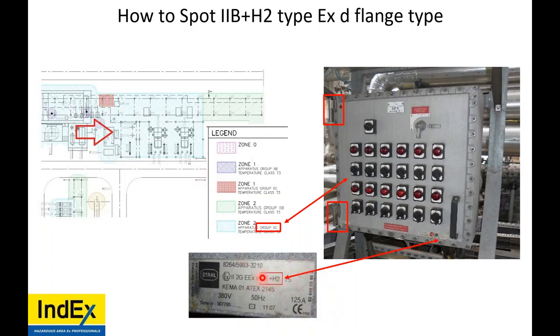Okay, so in this installation, they chose a IIB+H2. Now there are issues with that, as this will cause confusion between engineers and inspectors. Inspectors will perhaps say that this is not rated for a IIC area because during their training, they may not have been told about IIB+H2 being acceptable in a IIC area if the IIC area is only for hydrogen.